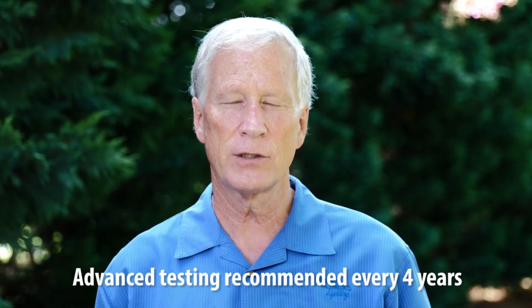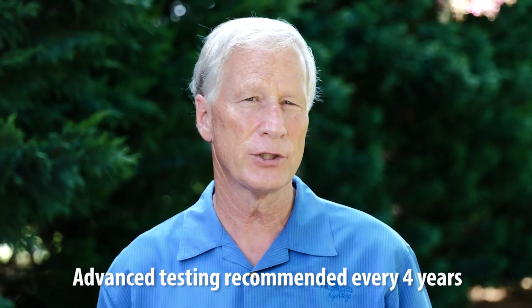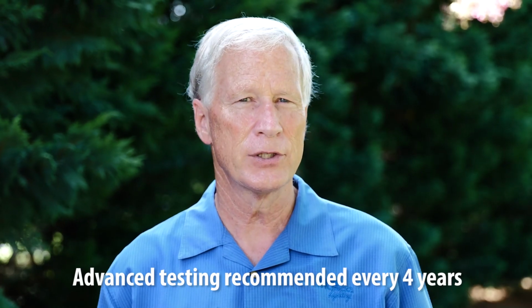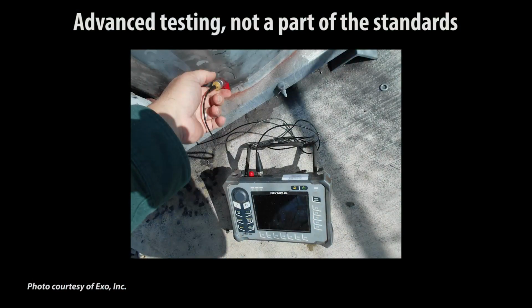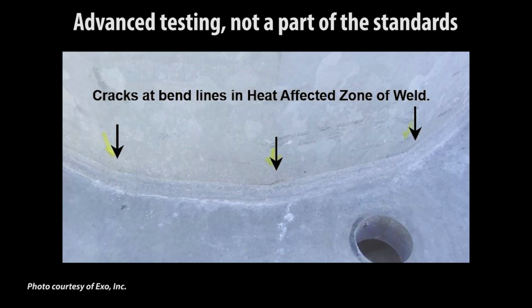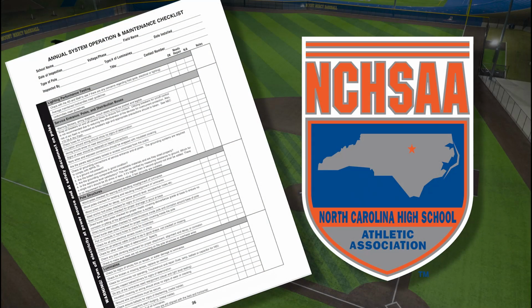This is where advanced physical inspection should occur when you see signs of corrosion. However, a test every 4 years should be a part of your routine maintenance. This advanced testing involves non-destructive testing using ultrasonic, magnetic particle, and dye penetrant technologies. It's used to help determine if there is corrosion or any other areas of concern within the walls or foundation of your poles, as well as with bolts and welds on the structure. Professionals such as EXO or Valmont would be an example of an appropriate testing service. Ensuring the safety and structural integrity of your sports lighting poles is crucial in order to avoid the significant damage that structure failures can create. Inspecting your pole structures annually is part of your safety checklist requirements.